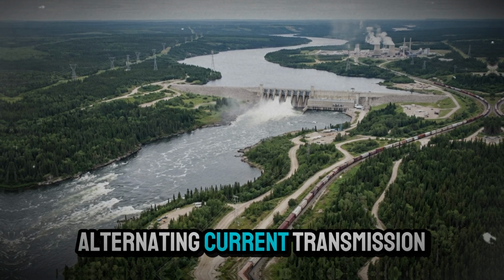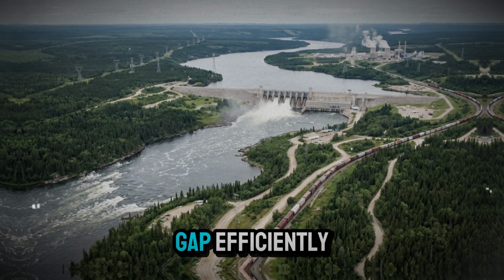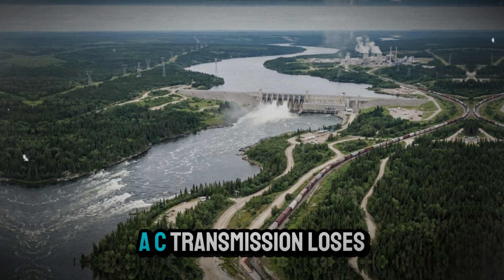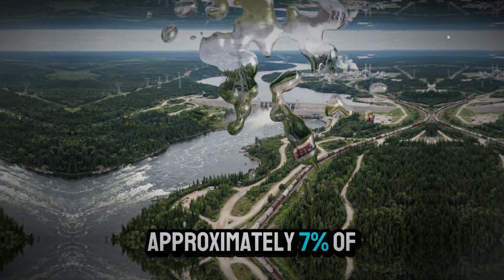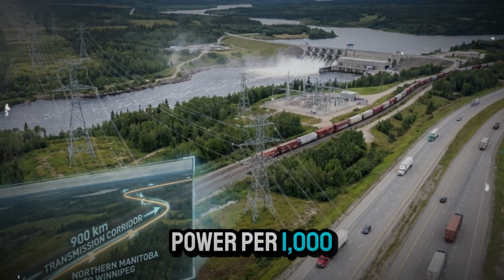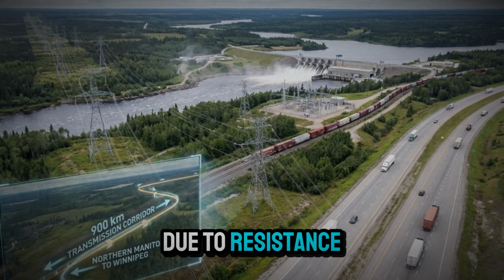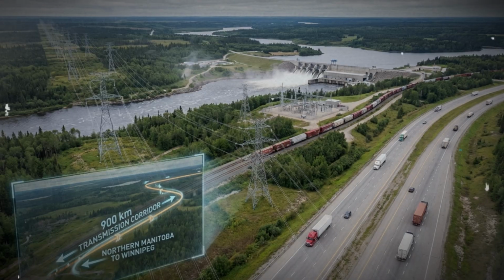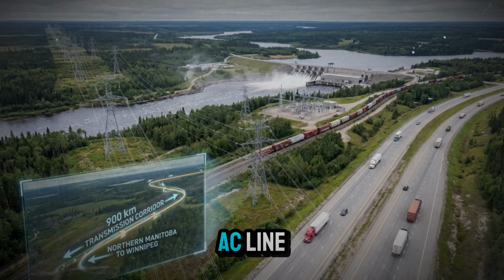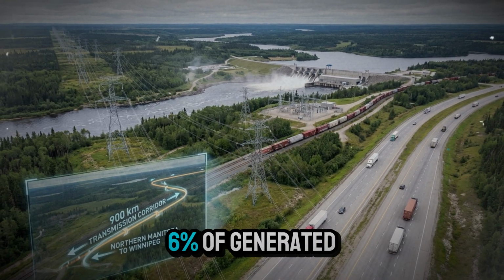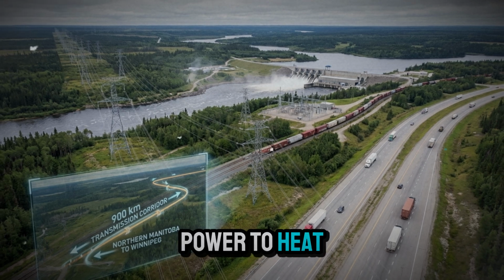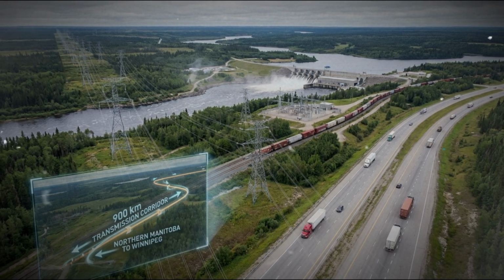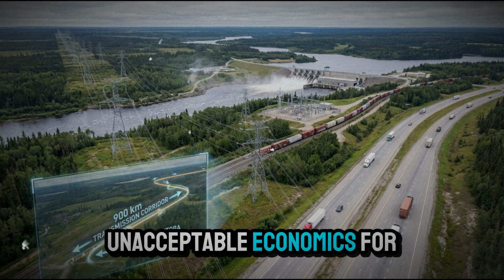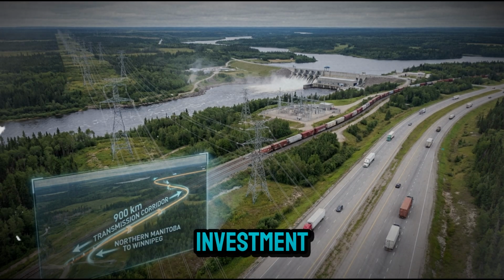Conventional alternating current transmission couldn't bridge that gap efficiently. AC transmission loses approximately 7% of power per 1,000 kilometers due to resistance and reactive losses. A 900-kilometer AC line would lose nearly 6% of generated power to heat before reaching Winnipeg. Unacceptable economics for a massive infrastructure investment.